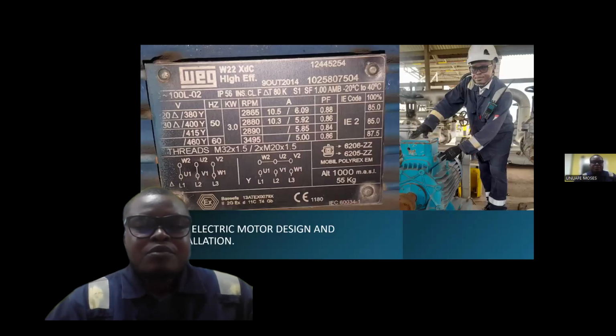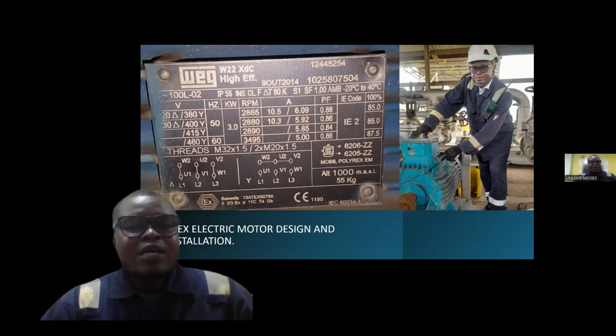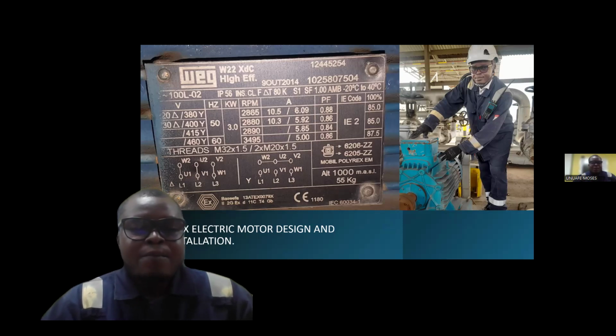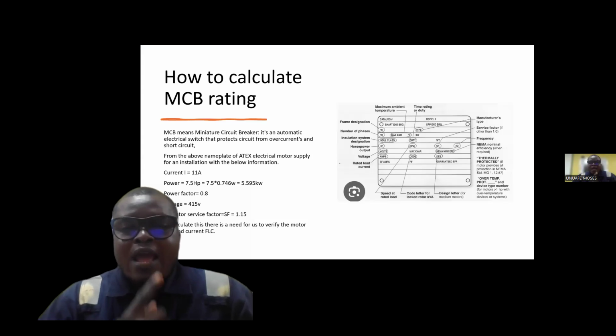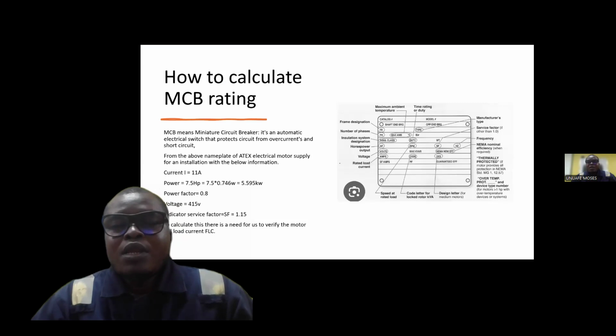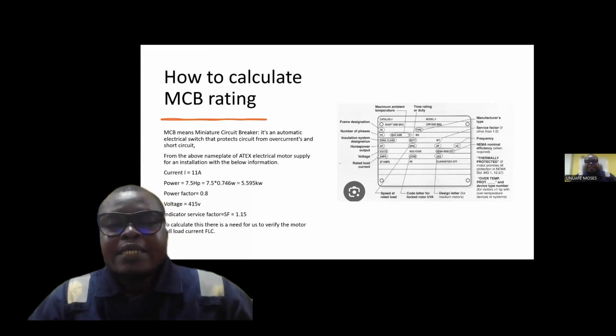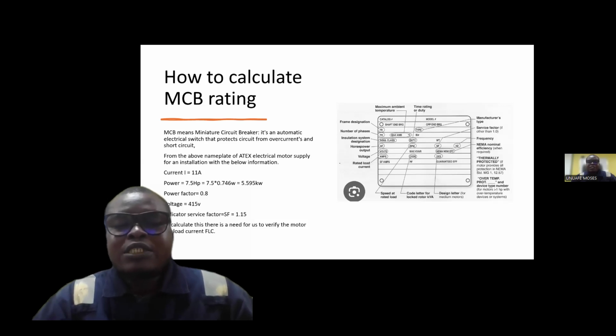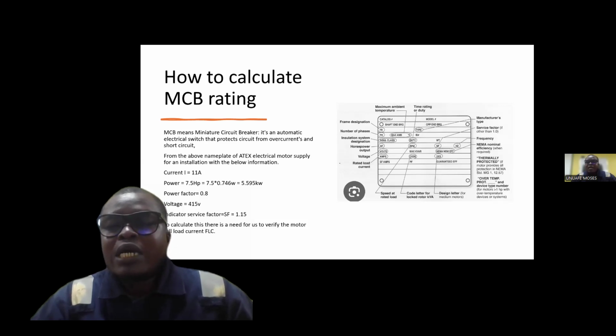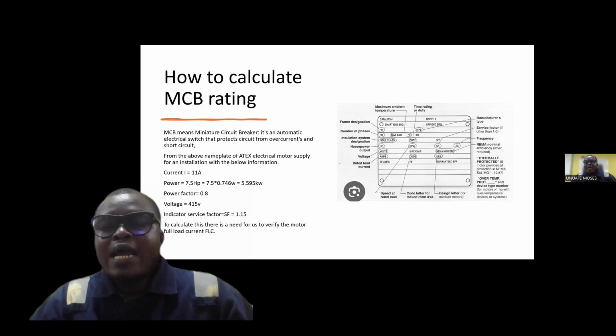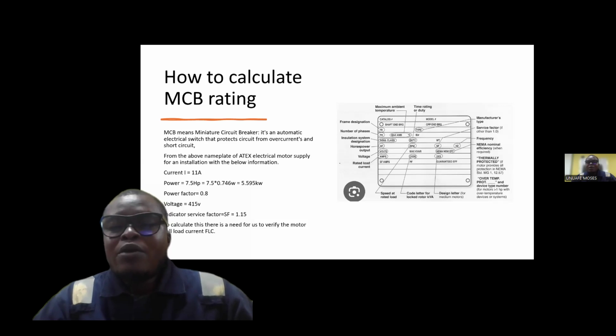Why do we have to do that? Let's take, for instance, in this scenario, let's consider an Atex motor that has been supplied for installation, and on it, we have a nameplate. On this nameplate, I want you to understand that on every nameplate, we have a prefix which indicates the frame designation, the number of phases, the insulation system design, and also voltage and manufacturer type and date. So there are so many other pieces of information like time rated duty, frequency, and so on.